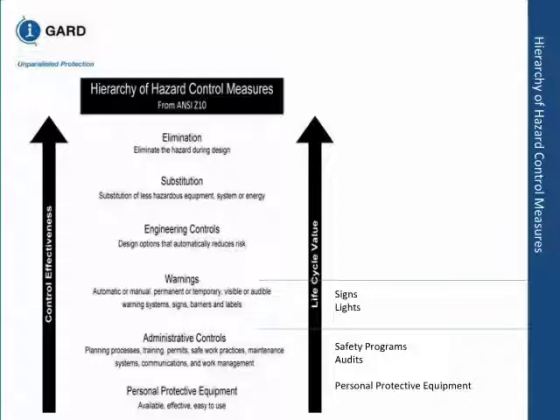So the best method, from the top down, is elimination or substitution. Elimination is harder because it requires a lot more effort. Substitution and engineering controls are more cost effective. Elimination you can do with high resistance grounding with insulated buses and a second fault priority system. Have you eliminated? You have eliminated 90 to 95% of the time, and that's pretty good odds.